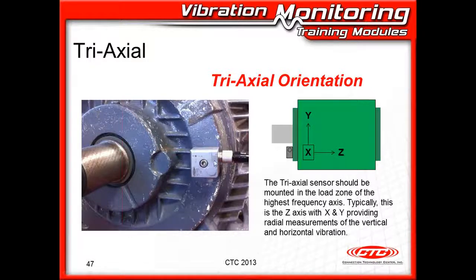And here is a triaxial accelerometer mounted onto a motor. Note that this is mounted in the axial direction. Remember, we'd like to have our best mounting in what would be our highest frequency direction. So we want the best mounting for the best frequency response. And typically, the axial direction will give the highest frequency.